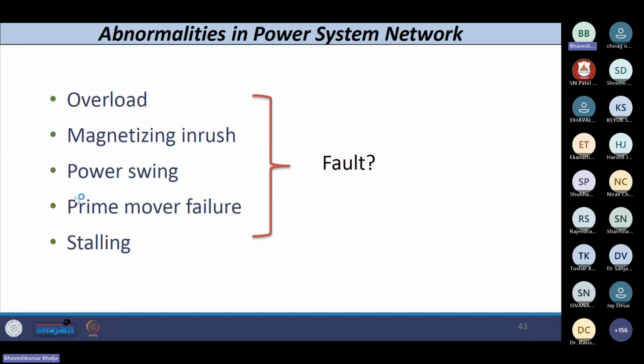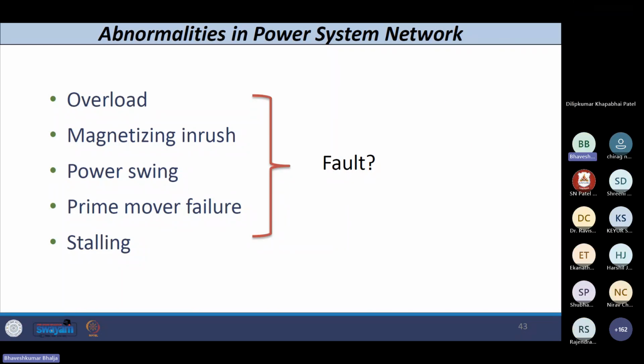And the fourth one is the prime mover failure. That means, whenever you have the failure of the turbine, we know that we are using turbines at power station level. If you have a coal based power plant, then we use some turbine. If we have a hydro based power plant, we go for Kaplan or Francis turbine. If we have a diesel generator, we have a diesel turbine. If we have a gas based power plant, we use a gas based turbine, and so on. So if the prime mover or turbine has failed, is there any harm to the generator?